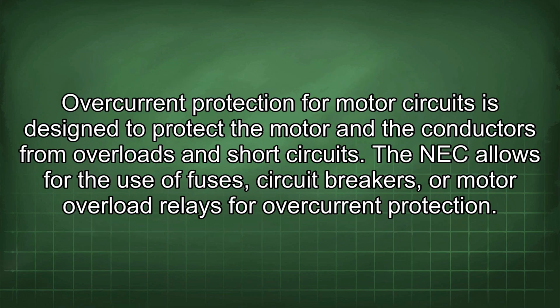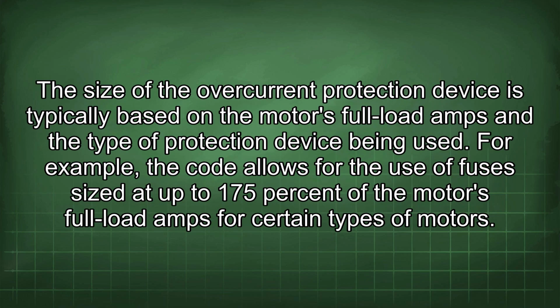Overcurrent protection for motor circuits is designed to protect the motor and the conductors from overloads and short circuits. The NEC allows for the use of fuses, circuit breakers, or motor overload relays for overcurrent protection. The size of the overcurrent protection device is typically based on the motor's full load amps and the type of protection device being used. For example, the code allows for the use of fuses sized at up to 175% of the motor's full load amps for certain types of motors.